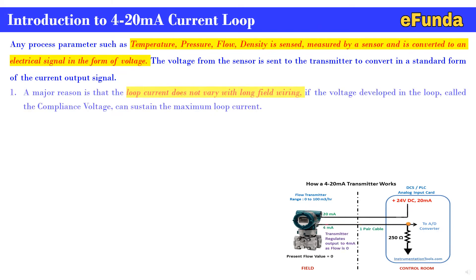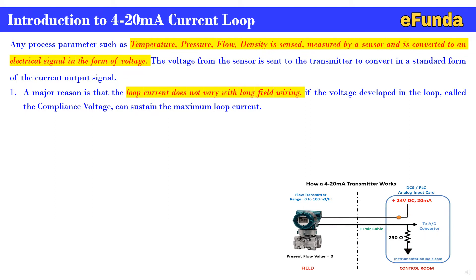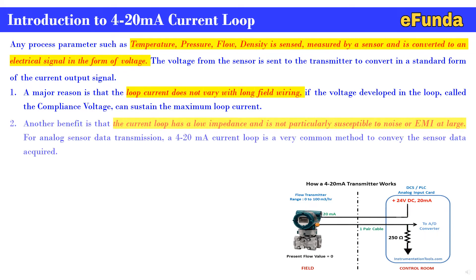A major reason for using 4 to 20 milliamp is that the loop current does not vary with long field wiring, provided the compliance voltage can sustain the maximum loop current. Another benefit is that the current loop has a low impedance and is not particularly susceptible to noise or EMI.